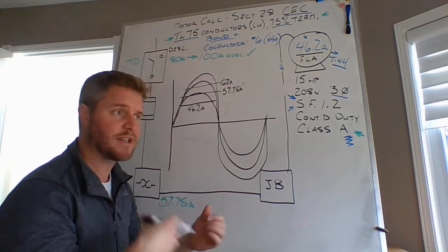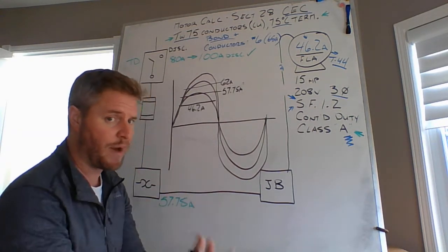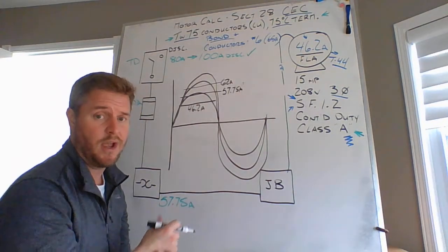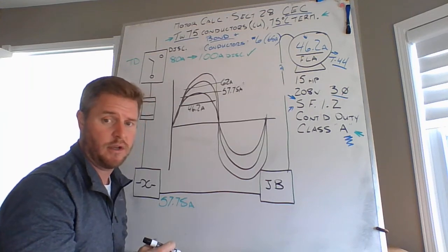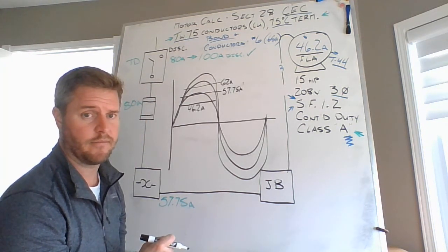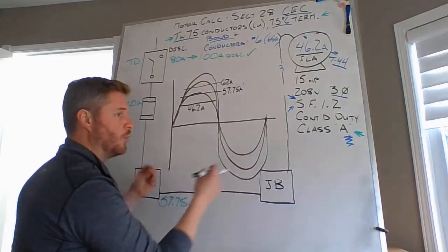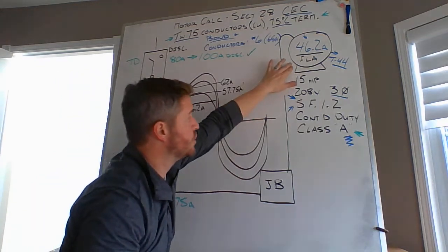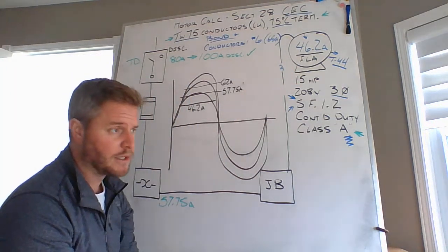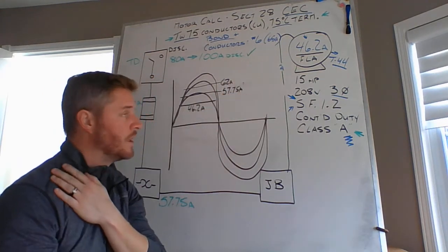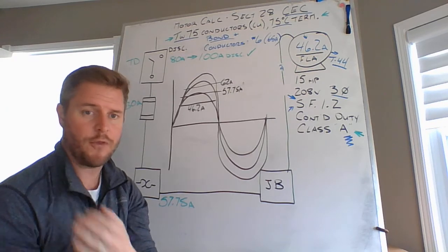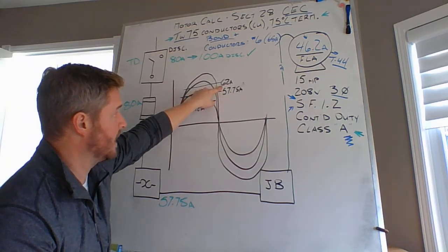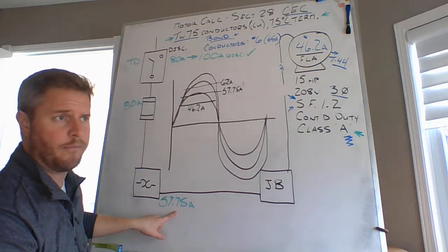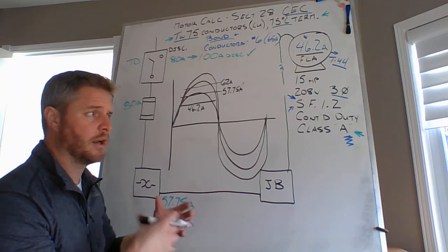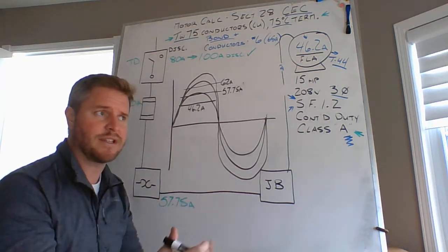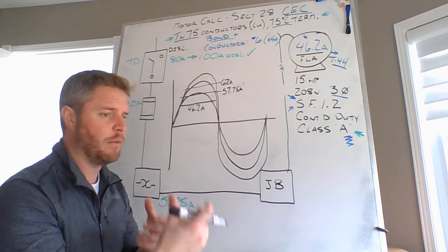And if you open the control circuit, it's the same as hitting the stop button. It means it's going to shut down everything. That motor stops its operation. You tried to make that motor do too much, and it can't handle it. So the overloads open, which opens your control circuit, effectively stopping the motor from running. And realistically, this motor should not be drawing anything more than 46.2 amps. Nothing more. And you're forcing it to draw 62 at this point in time. So your overloads say, no way, pal. You're done. I'm going to open. And you're going to take some time until I cool down, till I can reset myself. You hit my reset button. Then we'll try again.